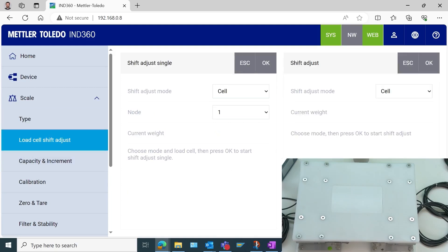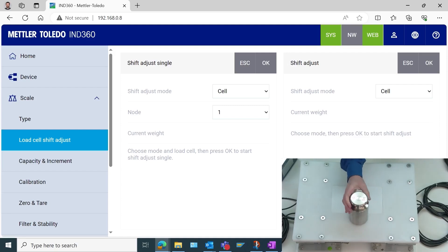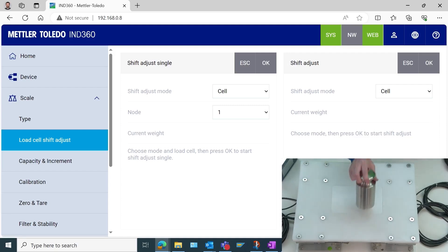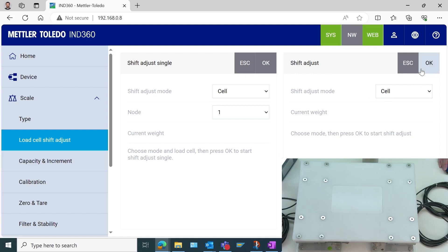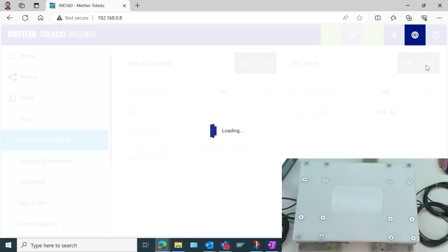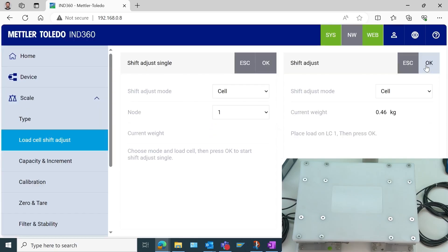The load cells shift adjust. We want this 5 kg test weight to weigh 5 kg whether it's here, whether it's here, or anywhere on this platform. So the shift adjust is going to help us make sure that that happens. I'm going to do the shift adjust on this right side, and the adjust mode is going to be by cell. It's asking me to empty the scale. It is empty, so I will select OK.